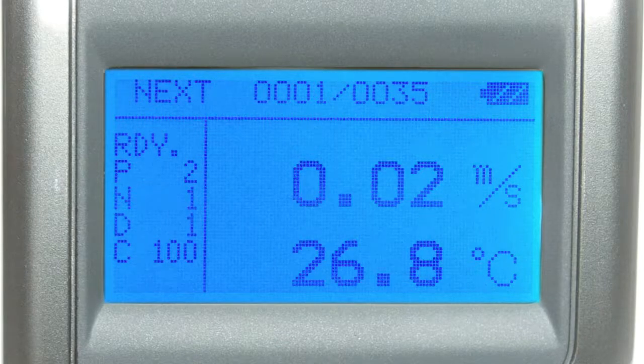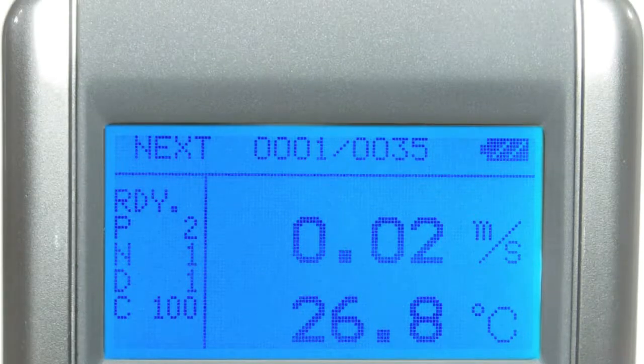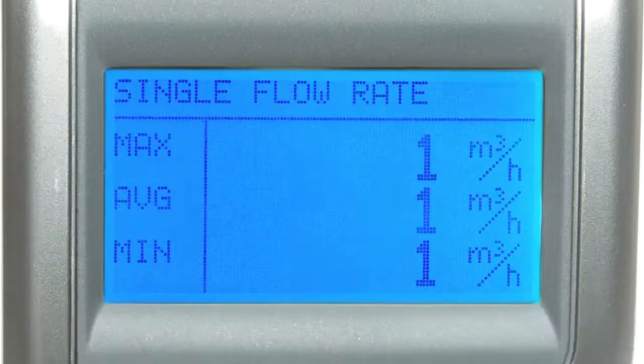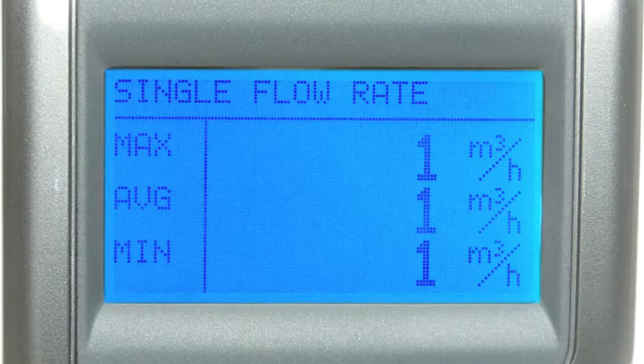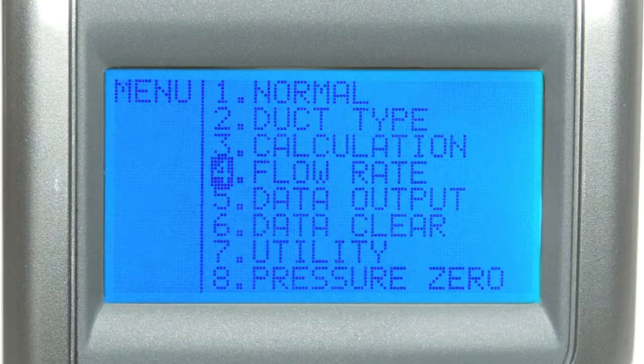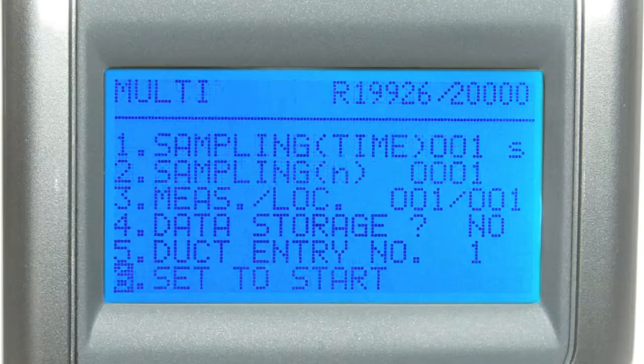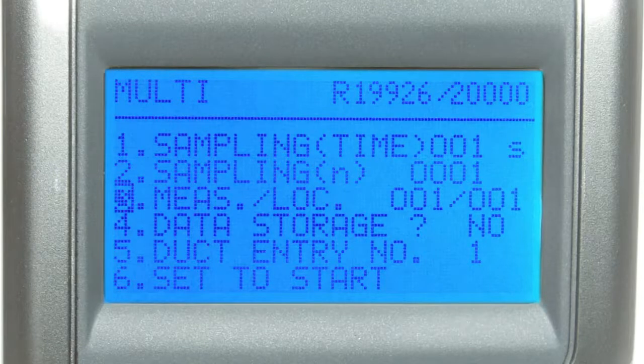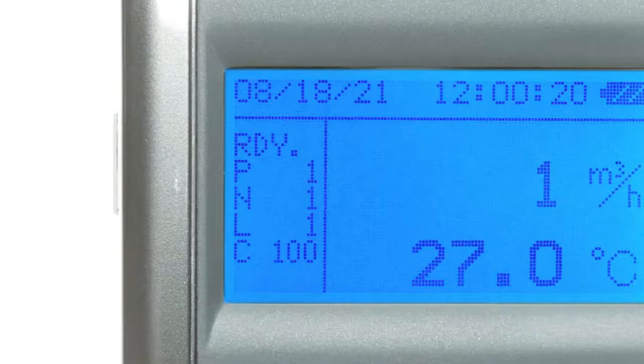After completing the measurement of point 1, the instrument will be in standby, ready to measure point 2. The number of samples already taken will be displayed with the total number of samples at the top of the screen. After the measurements are complete, you can review each parameter using the navigation buttons. And as with the calculation mode, you can press Menu to return to the main menu, or press Start or Hold to return to the setup screen for flow rate mode. If you selected Yes for data storage during setup, your results will be stored in the device's memory. Multi-flow rate is very similar to the single flow rate mode, except it adds an additional parameter for the number of locations. This allows you to take several airflow measurements to get a total average. On the ready screen, a new indicator, L, pops up, representing the number of locations for this measurement.